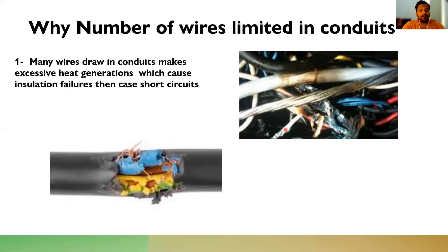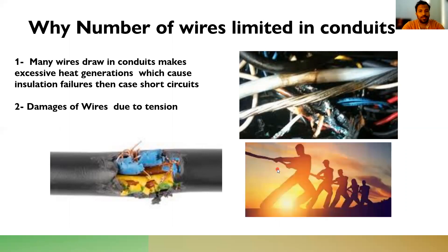And the second thing is that if you draw many wires inside the conduit, during pulling it's very difficult. And what will happen? It will be damaged also due to the pulling tension developed and the wires will be damaged inside the conduits. Therefore, you have to consider how many wires are limited inside the conduits as a major thing.